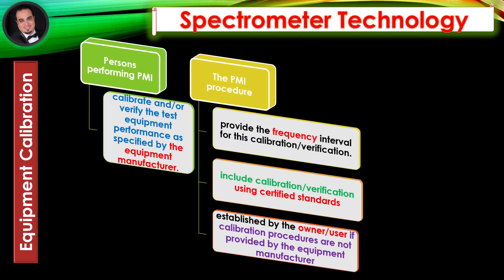Equipment Calibration: Persons performing PMI should calibrate and/or verify the test equipment performance as specified by the equipment manufacturer. The PMI procedure should provide the frequency interval for calibration verification, including calibration verification using certified standards established by the owner-user, if calibration procedures are not provided by the equipment manufacturer.